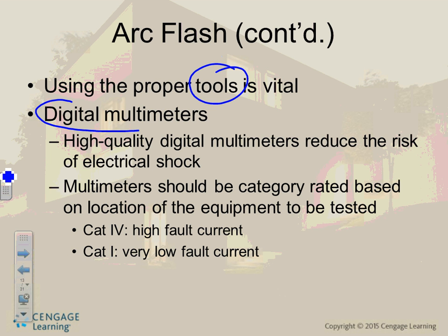And we have digital meters. When it comes to digital meters, guys, not all digital meters are created equal. There are stories of people using a digital meter that exploded right in front of them, burning their eyes. When you're using a digital meter, you want at least a category 4, like the one I have. You don't buy anything that's not category 4. The ones they sell for $15, like the meter you use in our labs, Ray, you can only use those on 120 circuits.